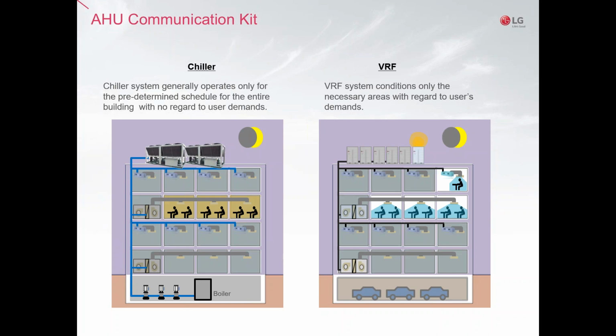So we don't necessarily need to replace the indoor units either. We can use the air handler unit communication kits and replace the water pipes or refrigerant pipes and put all the condensers on the roof, up to 360 feet from the indoor units, and save also a lot of space and carbon footprint.